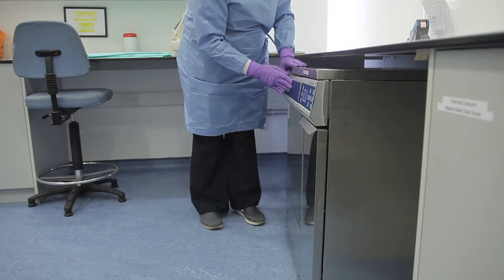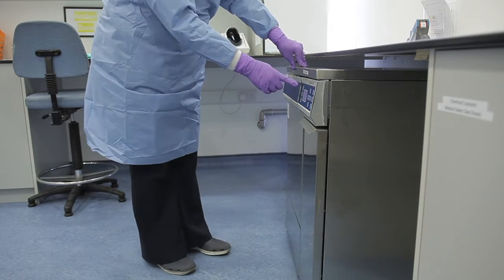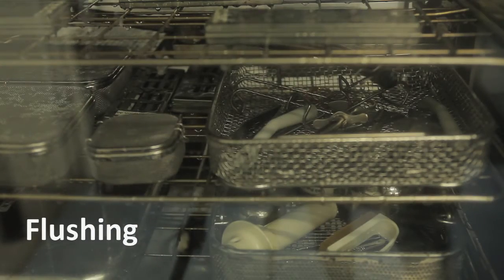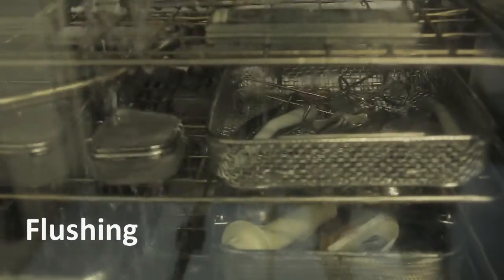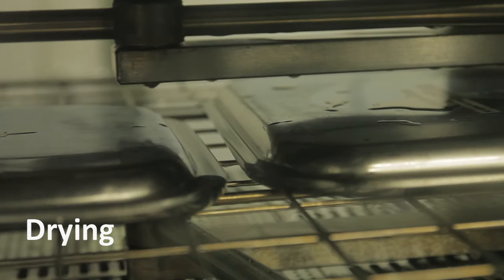The stages of washer disinfection are as follows. Flushing. This removes gross contamination from RIMD. Washing. Removes any remaining soil. Rinsing. Removes any additives used during the cleaning process. Disinfection. The temperature must reach a minimum of 90 degrees centigrade for 1 minute. Drying. This purges the load and chamber with heated air to remove residual moisture.